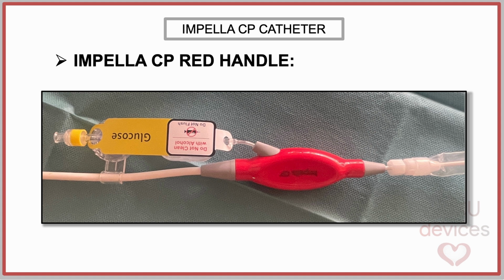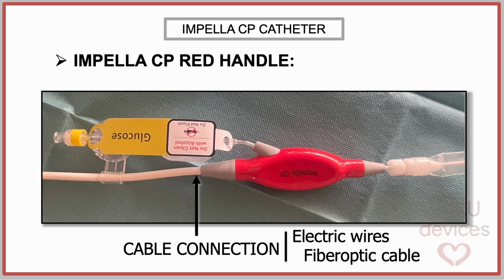The red hub serves as a convergence point for multiple system elements. From the distal end, the Impella catheter itself emerges, carrying within its lumen the three-phase power cable, the optical fiber, and the purge channel. On its lateral aspect, the purge line is connected via the side arm, ensuring continuous fluid delivery to the catheter system. And at its proximal end, it receives the white cable, which encloses the power lines, data wires, and the optical fiber.